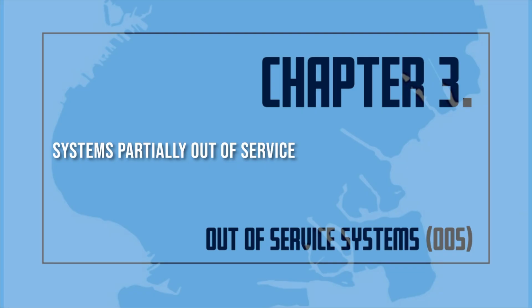Systems partially out of service. The impairment coordinator/building owner shall ensure that the local administrative fire company, a fire suppression piping contractor, fire department units, or master fire suppression contractor, Class A or B, has placed one blue disc, 8 to 9 inches in diameter, on all affected fire department connections. A red tag shall be placed at the main control valve and any closed sectional valve indicating the company name, date of removal from service, and anticipated return to service date.